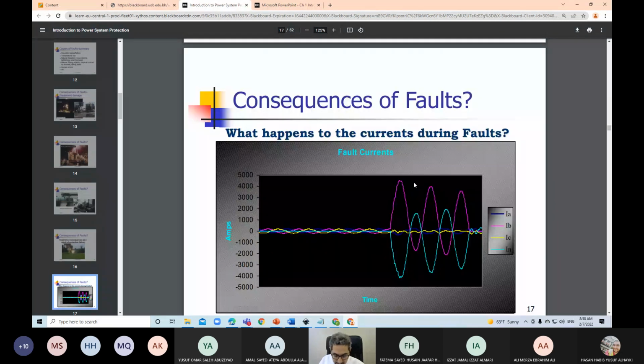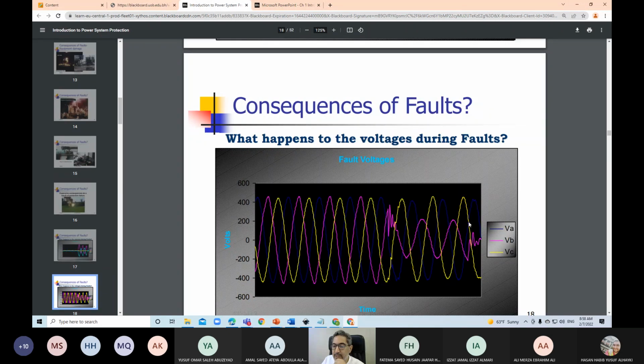During faults, there is a distinct increase. For the short circuit, the current will increase to very high values compared to the normal load currents, and sometimes can go to 20 or 30 times this value. Maybe this is a criterion based on which we can detect a short circuit: we monitor the current's values. The voltage, in some situations during shunt faults, will normally decrease. If the voltage persists low, this is also not good for the systems. Okay, we'll come to this later, inshallah.